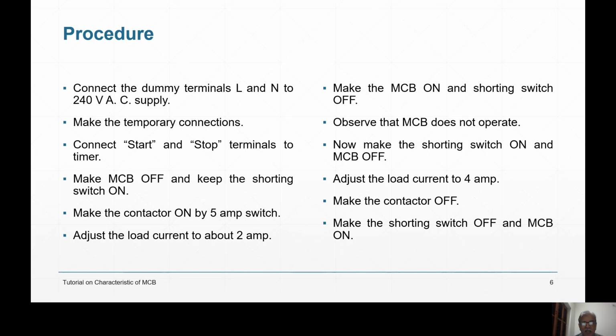And because of that, when you are doing any relay setting work, this is also very important. So we have bypassed the MCB just to adjust the current. Then we make the MCB on and shorting switch off. Observe that the MCB does not operate. It should not operate. Now make the shorting switch on again and MCB off. Adjust the load current to 4 ampere, double. Then we will go to 6 ampere. Then we will go to 8 ampere. So now we have gone to 4 ampere.